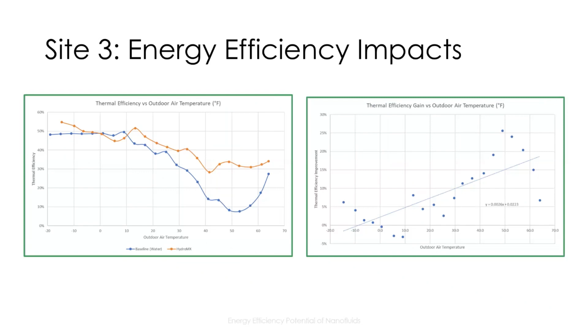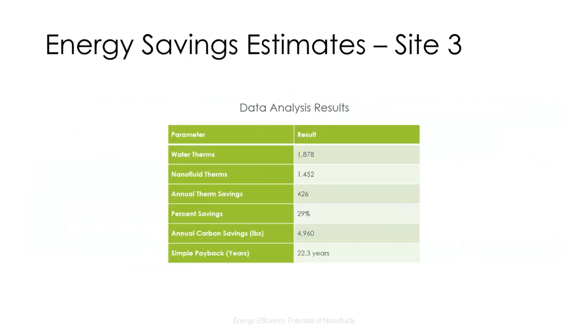The chart on the right shows a scattershot of points, but the intent here is to show that the gain in calculated thermal efficiency after the nanofluid installation is most significant at mild outdoor air conditions when the heating loads are the lightest. So the results of our analysis showed that we gained positive energy savings. However, the incompleteness of the data and capturing the loading makes it hard to draw confident conclusions from this site.